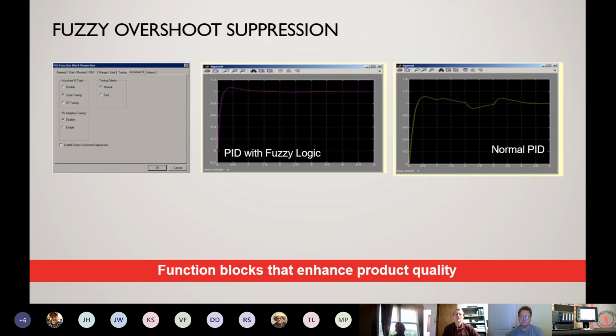Not all normal PID loops look like that, but if you have one that is looking like that when you do a trend, you might want to enable the fuzzy logic. Like I said, it's the same fuzzy logic that's used in the UDC, and they've embedded it into the CPU of the HC900.